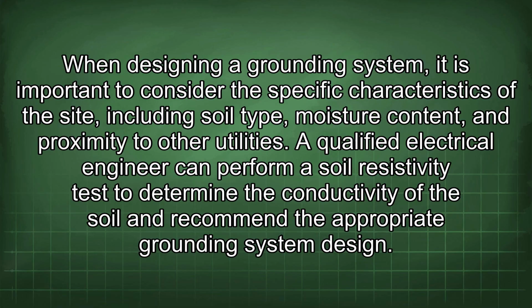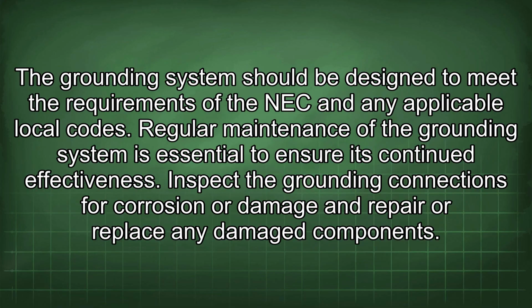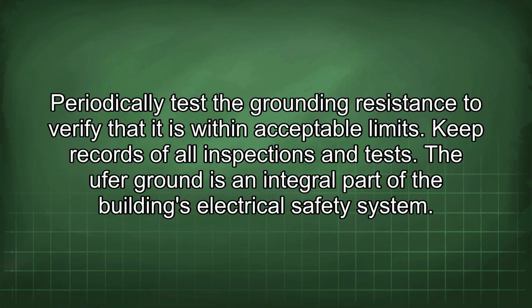A qualified electrical engineer can perform a soil resistivity test to determine the conductivity of the soil and recommend the appropriate grounding system design. The grounding system should be designed to meet the requirements of the NEC and any applicable local codes. Regular maintenance of the grounding system is essential to ensure its continued effectiveness. Inspect the grounding connections for corrosion or damage and repair or replace any damaged components. Periodically test the grounding resistance to verify that it is within acceptable limits. Keep records of all inspections and tests.